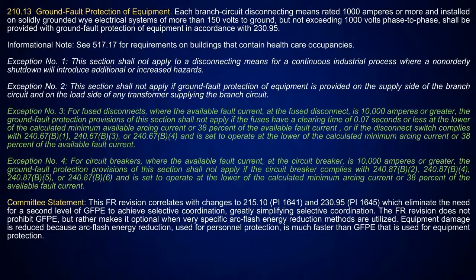Now, there was another thing that happened here in 210.13, and basically this is to put it in compliance with 215.10 and 230.95. This is where you're getting into your feeders in Article 215 and your services at Article 230, and this is to help eliminate the need for a second level of ground fault protection of equipment to achieve your selective coordination. Basically, when you're looking at exception 3 and 4 and tying all this in, all this is doing is tying in that you already have something set up over here that means you don't need a second level because you may have already provided it at the other location.